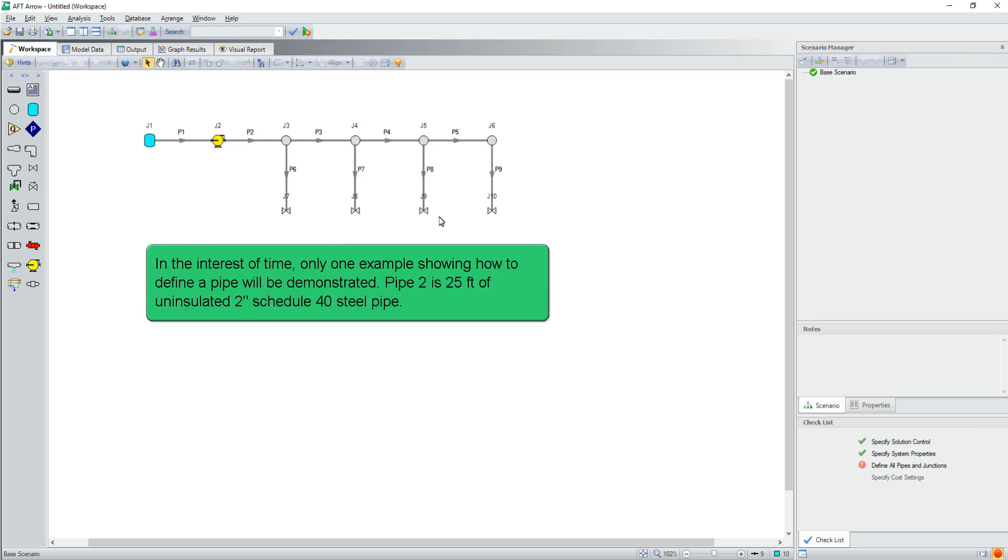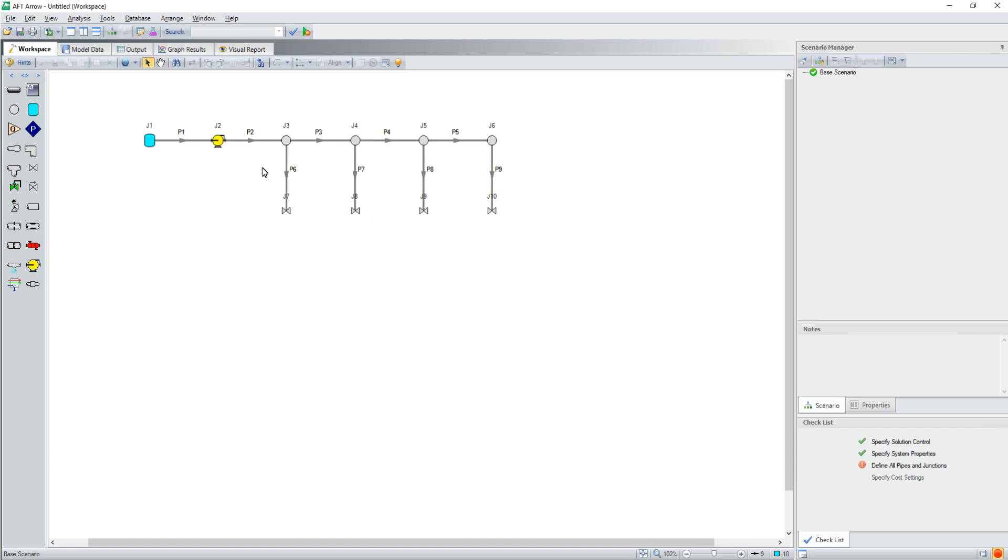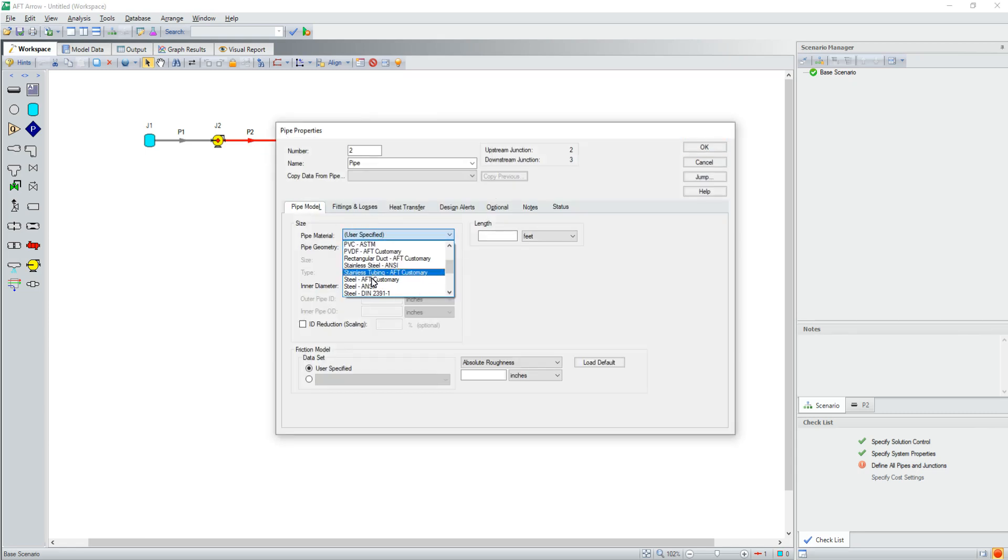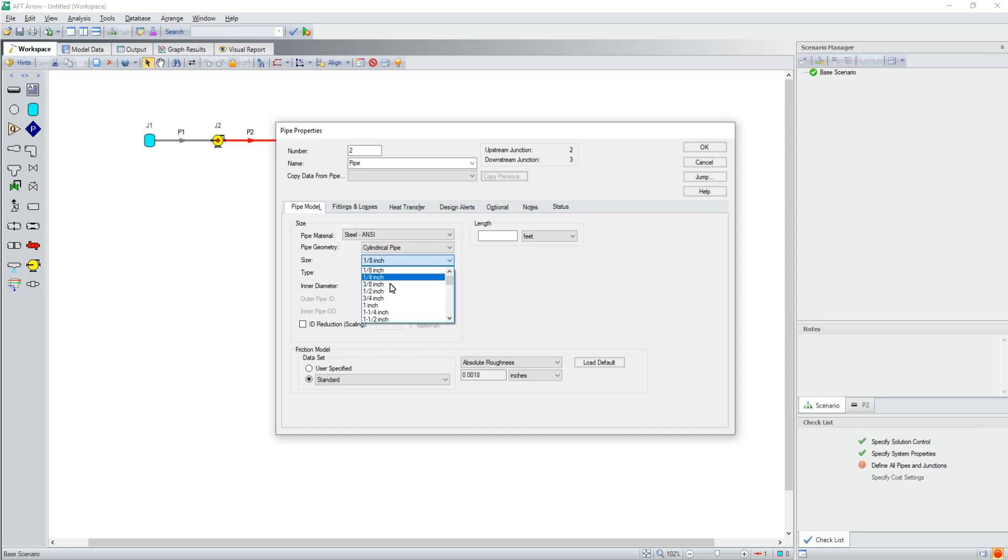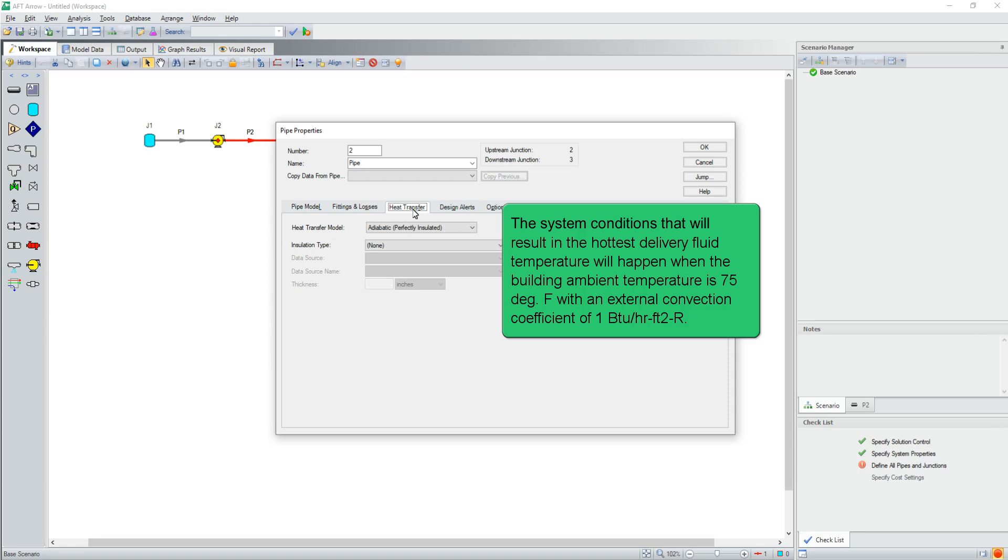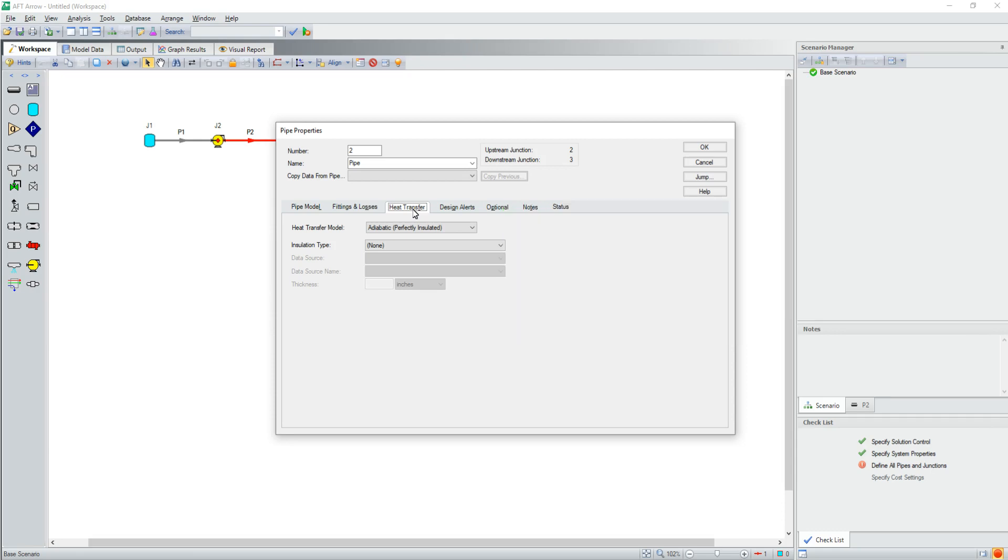In the interest of time, only one example showing how to define a pipe will be demonstrated. Pipe 2 is 25 feet of uninsulated 2-inch Schedule 40 steel pipe. The system conditions that will result in the hottest delivery fluid temperature will happen when the building ambient temperature is 75 degrees with an external convection coefficient of 1 BTU per hour foot squared Rankine.